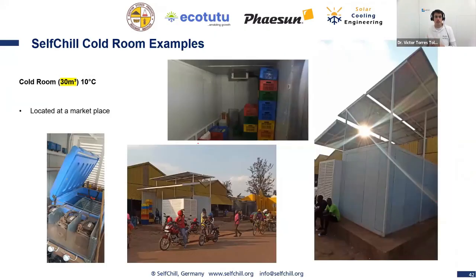Okay, let's have a look at another sample. A very interesting example in Kigali, Rwanda, at a marketplace. Because Rwanda has quite low ambient temperatures, here we can work with 6 cooling units on a bigger cold room, 30 cubic meters, 10 degrees. So everything is a question of design.